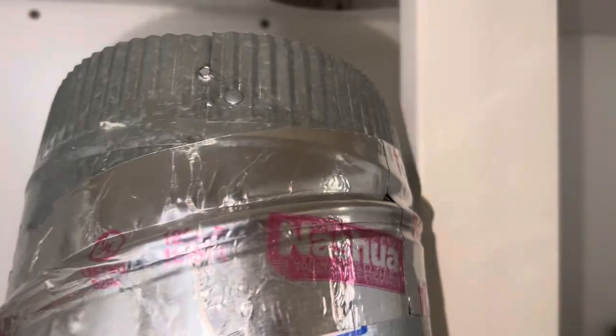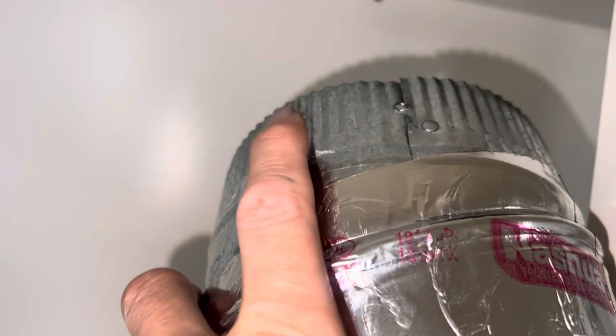The next thing is to tape up. Before, this was on the outside of that. That's totally wrong. You never put the lip part that's supposed to taper inwards with the airflow going up. You never put it on the outside.